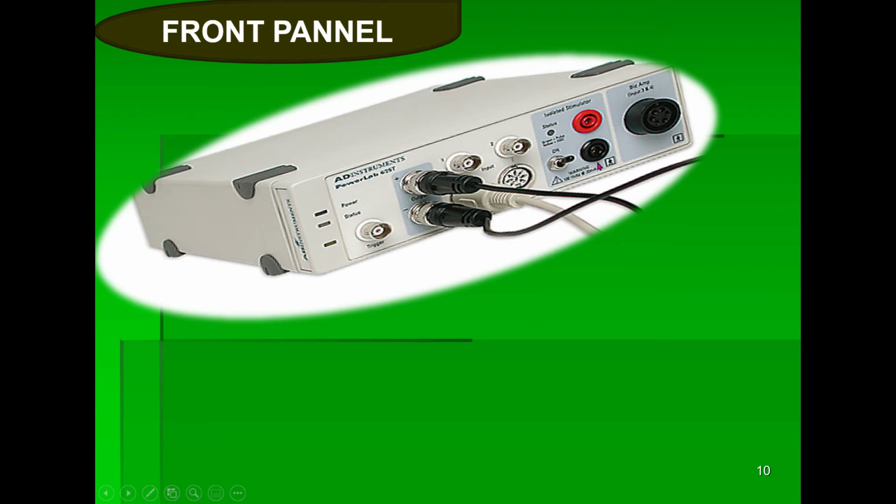But you can see red and black. These connectors are for the connecting wires for stimulation to the human subject. When we perform the EMG technique, we need to stimulate the human nerves. For that purpose, we have a special type of stimulating electrode that we attach to this human stimulator panel, and then Power Lab will generate a small amount of current so that it will stimulate the nerve of the human subject, and data will be recorded with this bioamplifier cable.